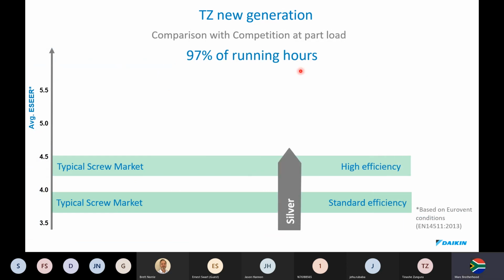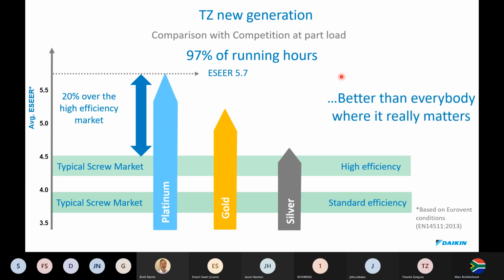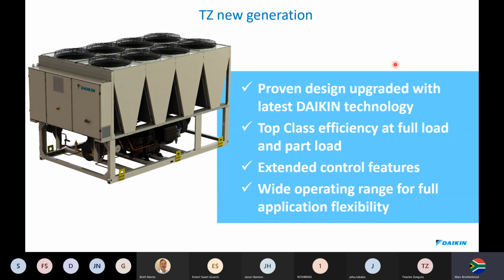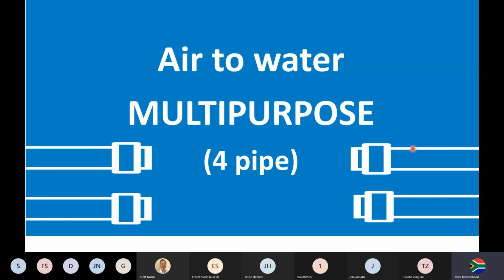And if we look at 97% of running hours at part load, generally if a typical screw market, we've evaluated the whole market, you're running at part load 97% of the time. All the opposition chillers use on average 4.5 ESEER in screws in high efficiency and their standard chillers. So we're up to 20% energy saving on our platinum range, which is huge on energy bills. So ultimately, the inverter chiller is a proven design upgraded with Daikin's latest technology, top class efficiency at part load, extended control features, and wide operating ranges, be it ambient temperatures, be it water temperatures.